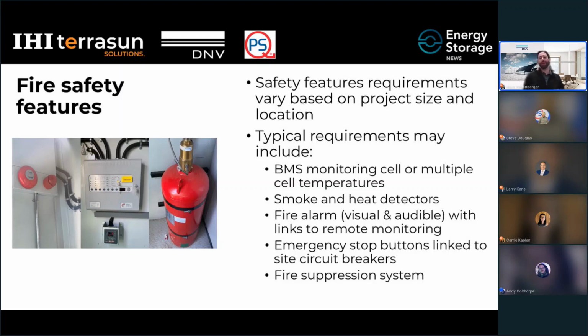So I talked a little bit about smoke and heat detectors. There's also a new class of detector coming on in the lithium-ion BESS space right now, which are electrolyte vapor detection systems. These systems look for fine particulate matter generated from the electrolyte within lithium-ion batteries and promise to offer earlier detection signals that the energy management system within the BESS can act on to prevent thermal runaway.